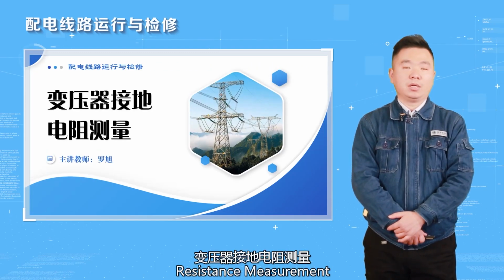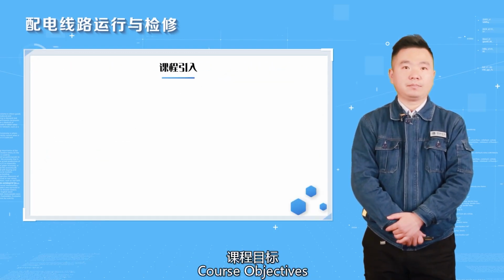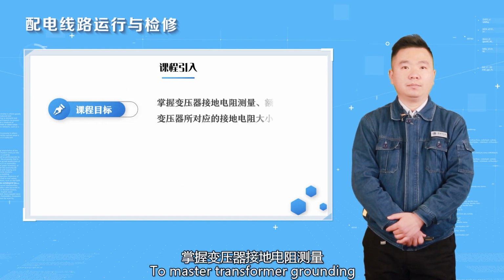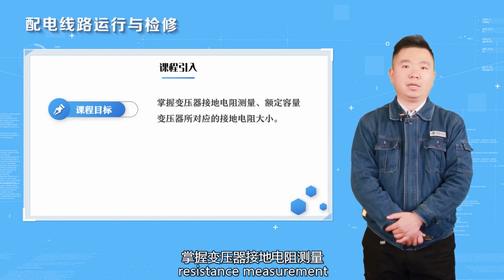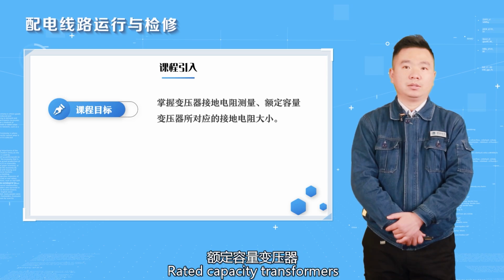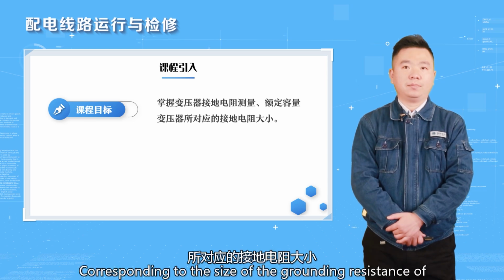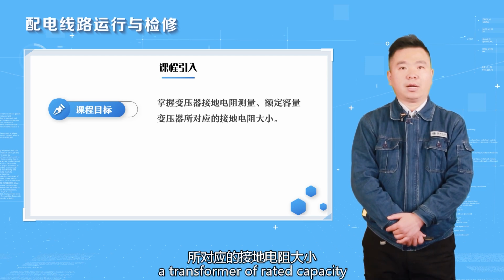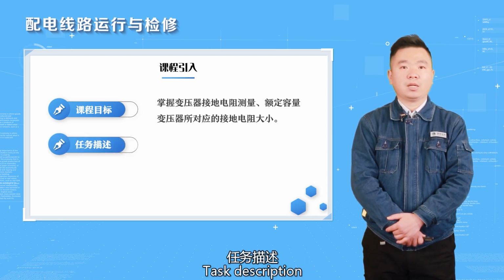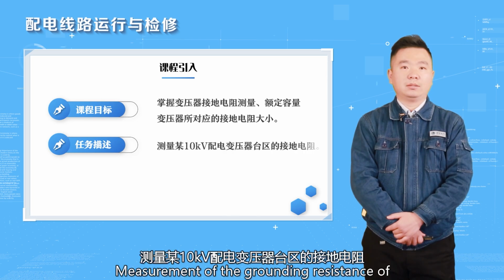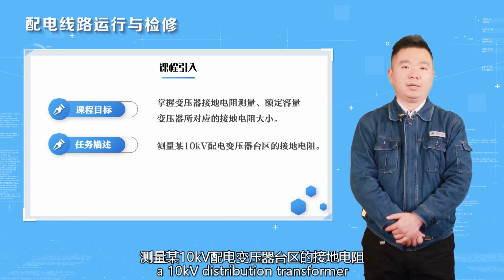Transformer grounding resistance measurement. Course objectives: to master transformer grounding resistance measurement. Rated capacity transformers correspond to the size of the grounding resistance of a transformer of rated capacity. Task description: measurement of the grounding resistance of a 10 kV distribution transformer.